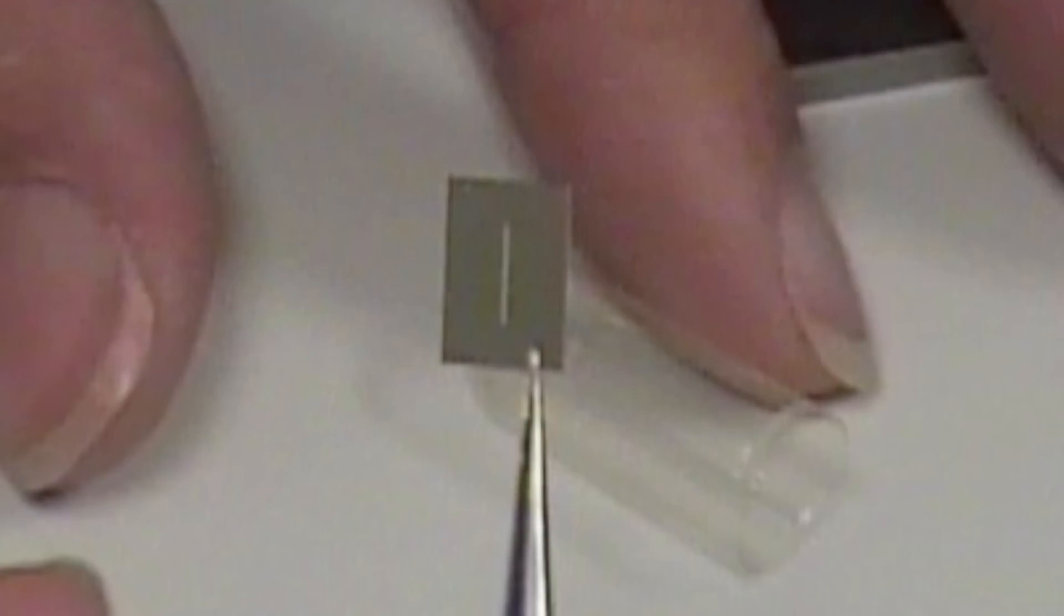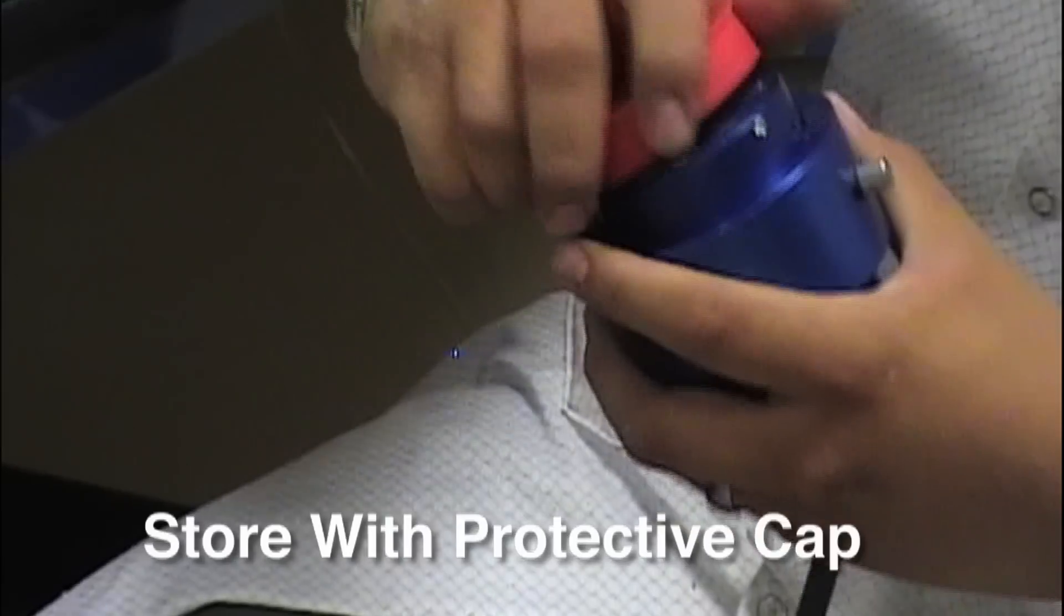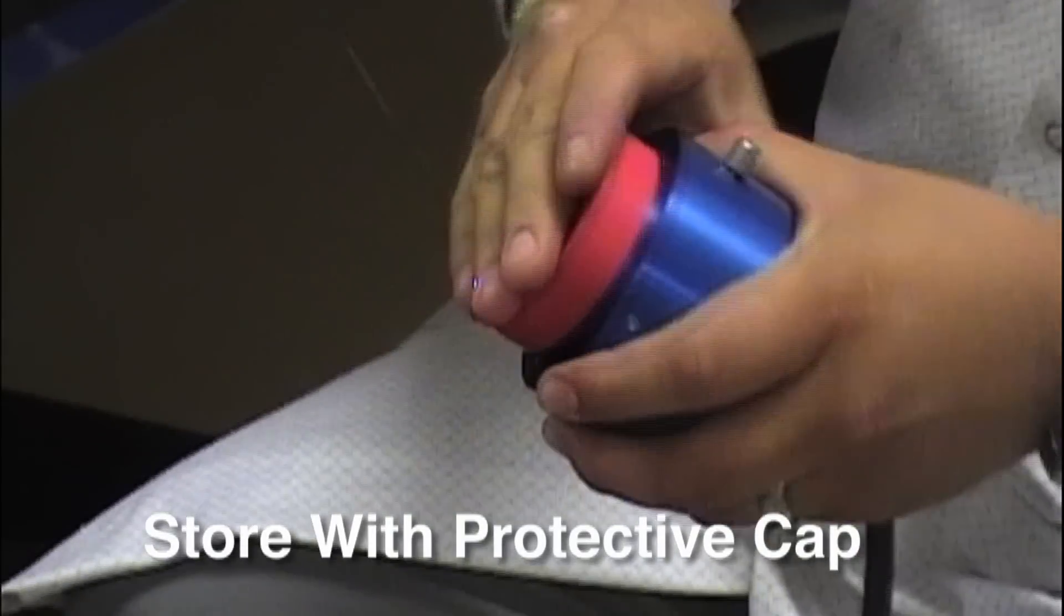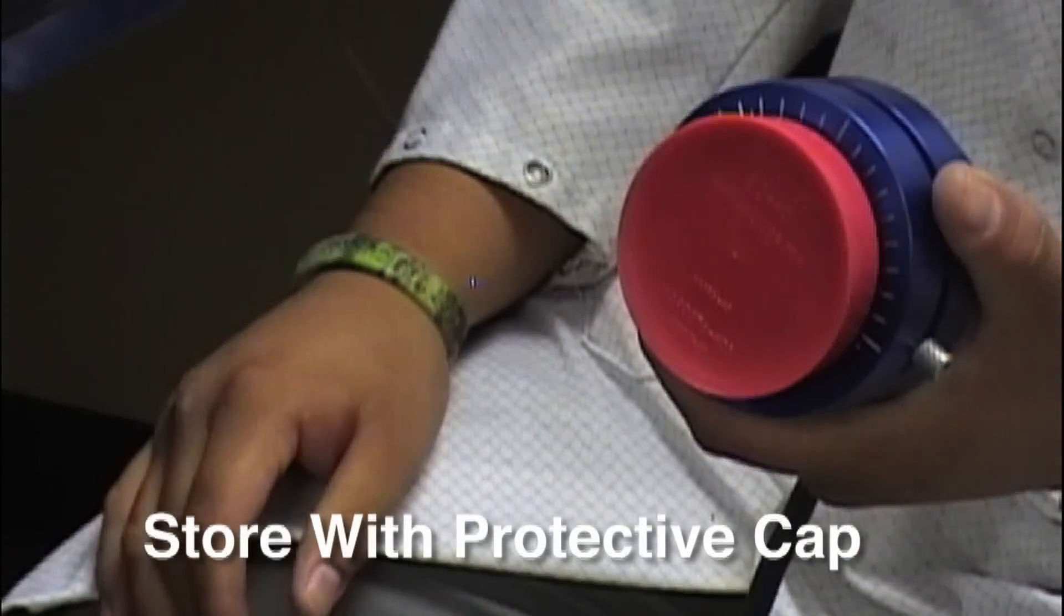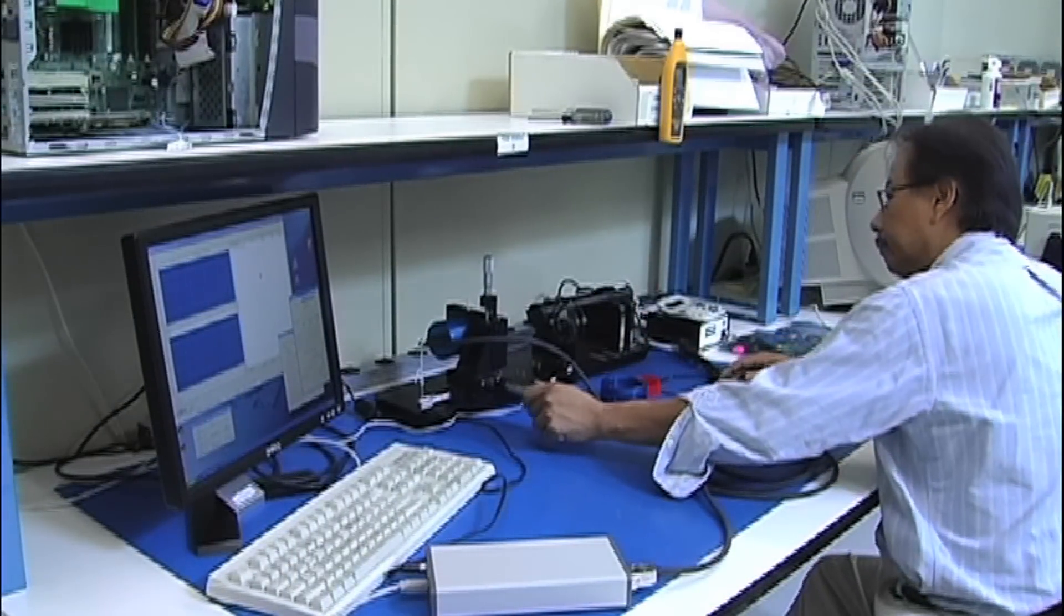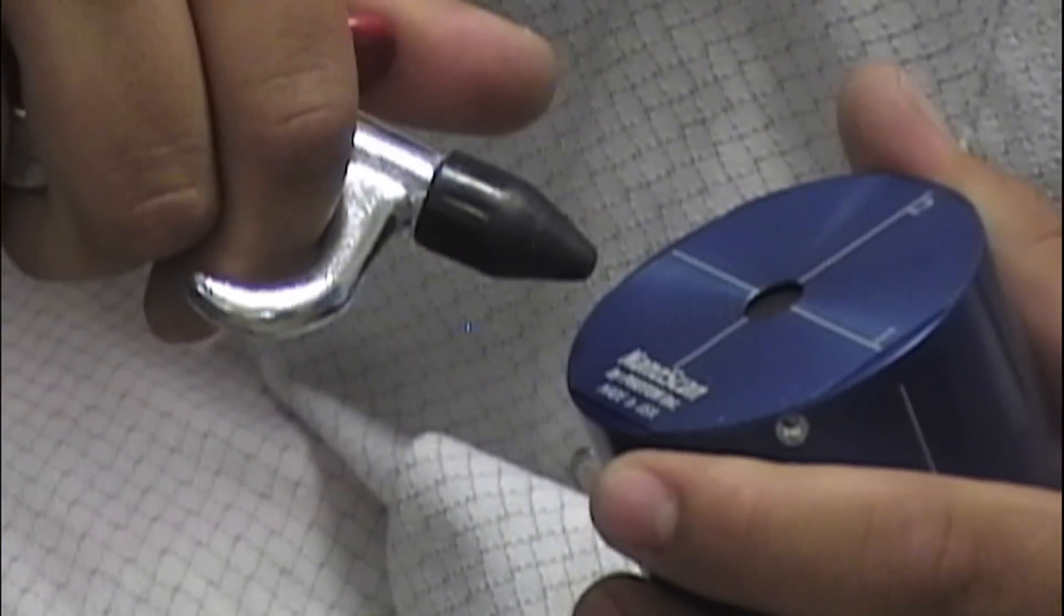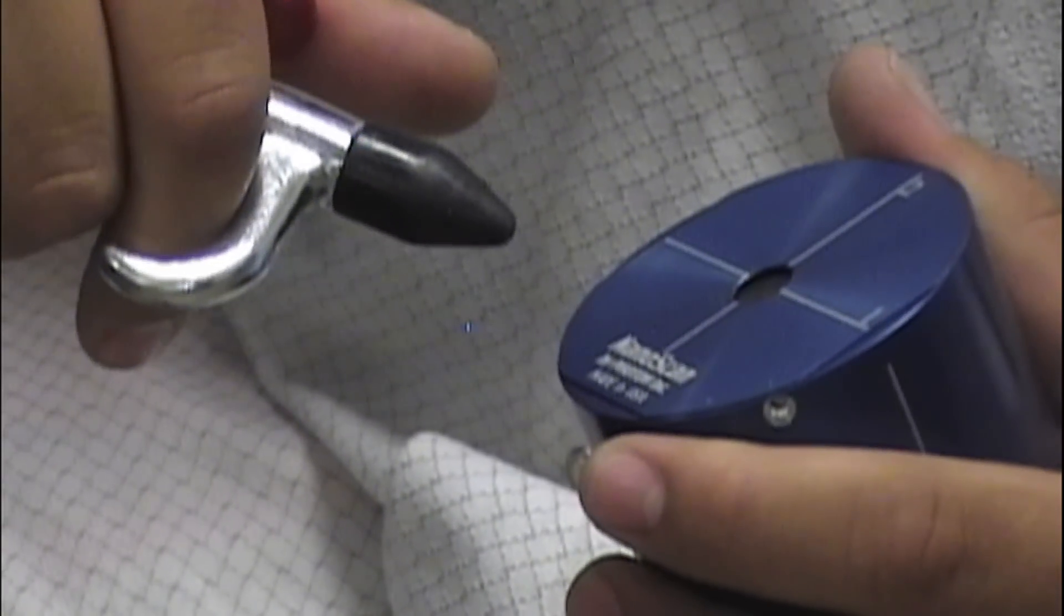Debris such as dust particles can lodge in the very fine openings of the slits or pinholes. Therefore, when the system is not in use, it is recommended that the protective plastic cap be used to cover the scan head entrance aperture. If inconsistent performance is observed and contamination by debris is suspected, a clean jet of compressed gas may solve the problem.